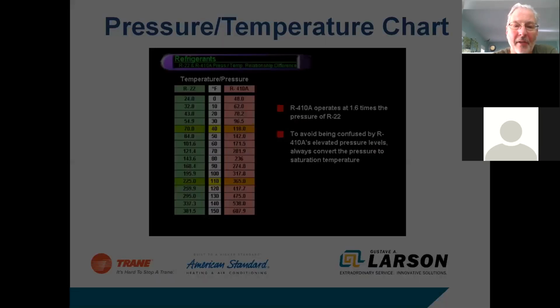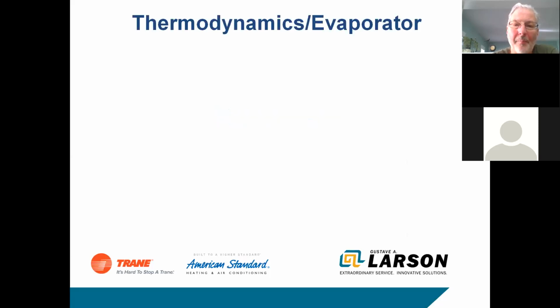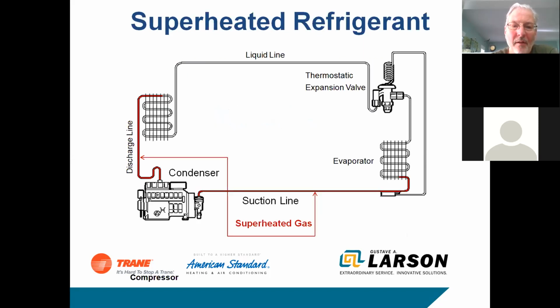Okay. I'm going to skip by some of this, guys. So we want to get to just superheat. So on a system that has an expansion valve, we charge by subcool, but we monitor the superheat. So in other words, we charge to 10 degrees subcool. All that's telling us is that we've got high pressure vapor leaving the compressor. We're hitting the condenser and we're condensing that high pressure vapor back into a liquid. We're sending liquid to the expansion valve. The expansion valve has to see liquid in order for it to work properly. And the expansion valve is metering out a saturated vapor liquid low pressure. And the evaporator is picking up heat, and that superheated gas is going back to the compressor. So on an expansion valve system, we like to charge to 10 degrees of subcool.